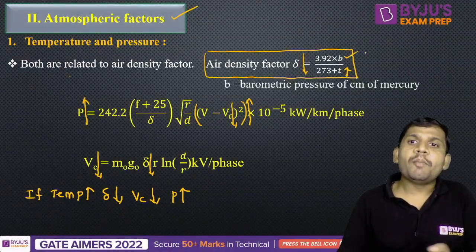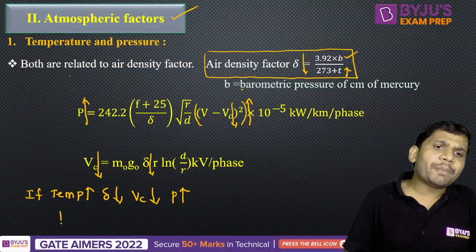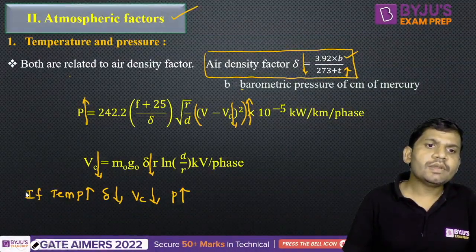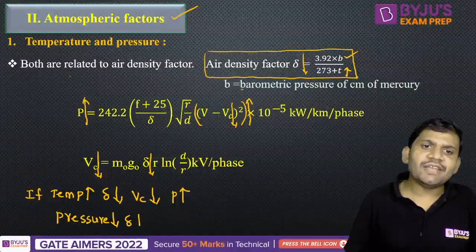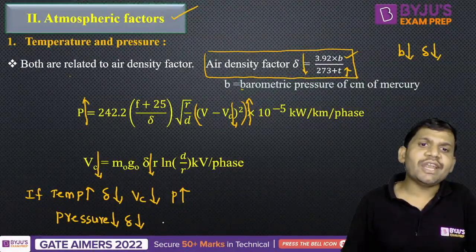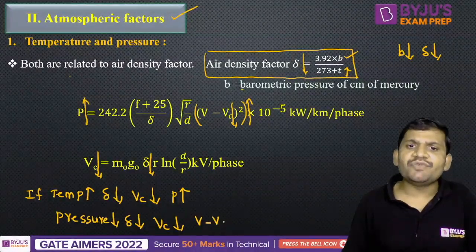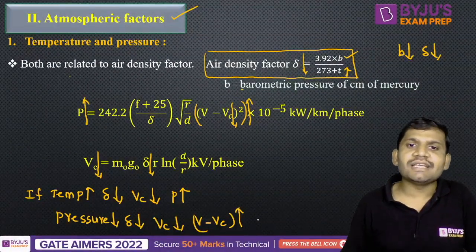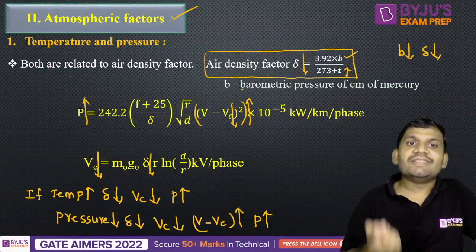Considering pressure — where B is the barometric pressure in centimeters of mercury — if pressure reduces, the air density factor also reduces. If the air density factor reduces, then the critical disruptive voltage reduces. If the critical disruptive voltage reduces, V minus Vc increases, so the corona loss also increases. Like this, corona loss depends on both temperature and pressure.